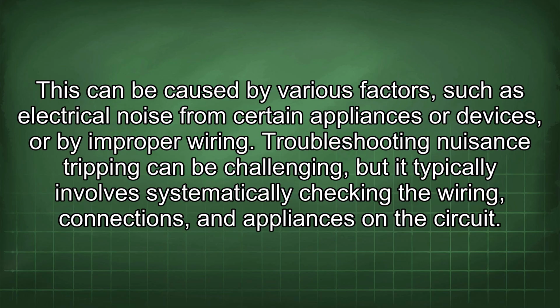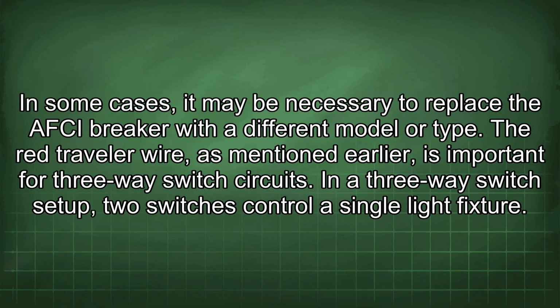This can be caused by various factors, such as electrical noise from certain appliances or devices, or by improper wiring. Troubleshooting nuisance tripping can be challenging, but it typically involves systematically checking the wiring, connections, and appliances in the circuit. In some cases, it may be necessary to replace the AFCI breaker with a different model or type.